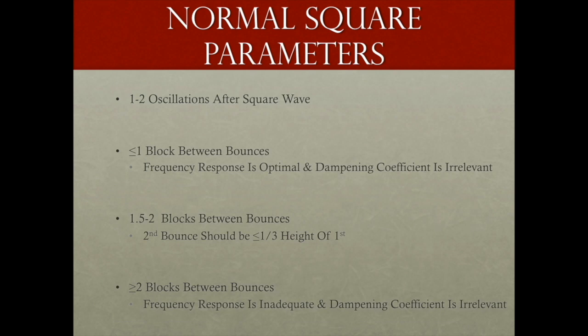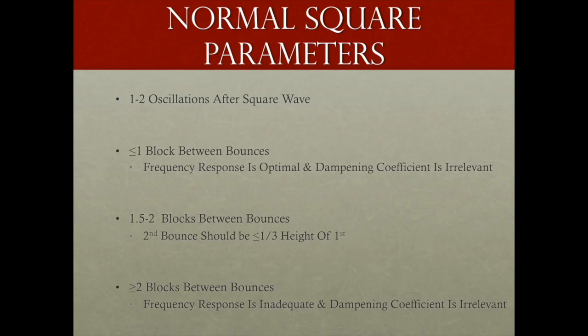The parameters of a normal square wave test are that there are at least 1 to 2 oscillations after the square wave, with less than 1 block between bounces. If this is the case, the frequency response of the system is optimal. If there are 1 to 2 blocks between bounces, this is when you care about dampening—you want adequate dampening such that the second bounce is less than 1/3 the height of the first bounce. If there are greater than 2 blocks between bounces, the resonant frequency response is also inadequate.